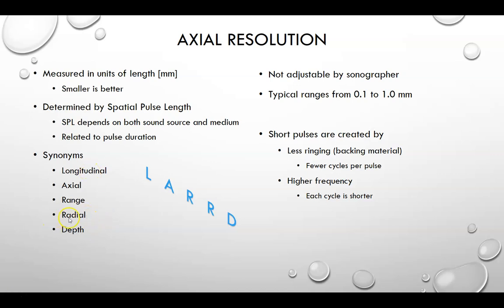That explains why we also call it radial resolution. And depth resolution is another synonym for range. The axial resolution is not adjustable by the sonographer unless we were able to adjust the frequency. But even then, we don't know how many cycles the manufacturer adds if we go up in frequency — they might add 10 cycles going from 4 to 8 megahertz. So we just don't know how to necessarily adjust the axial resolution.